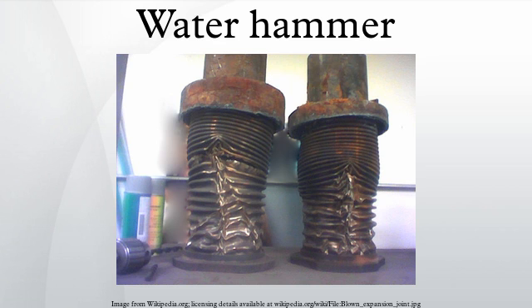The latter follows from a series of hydraulic concepts: compressibility of the liquid, defined by its adiabatic compressibility modulus BL, resulting from the equation of state of the liquid generally available from thermodynamic tables. The elasticity of the walls of the pipe, which defines a modulus of equivalent compressibility.